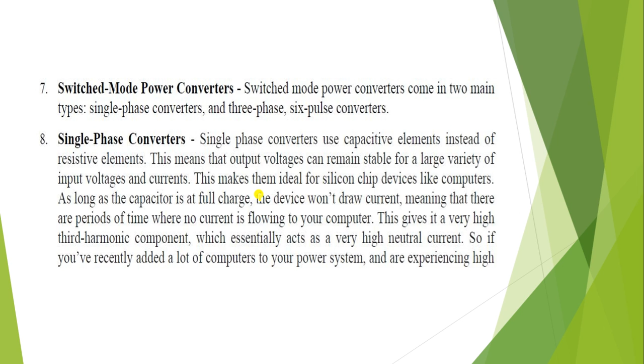This gives it a very high third harmonic component, which essentially acts as a very high neutral current. So if you have recently added a lot of computers to your power system and are experiencing high neutral current, this may be the cause. The third harmonic can be as high as 81% of the value of the main current.